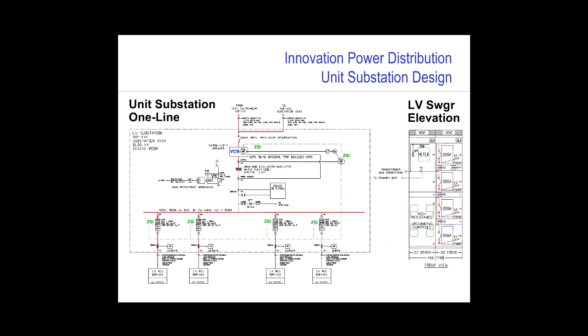So let's summarize what we've discussed today. Let's take a look at, if we had a blank piece of paper, what would today's perfect unit substation look like? Well, I've included here at least my idea of a perfect unit substation. As you can see in the one line, it's fed from a 15 kV source into a load break switch and a primary vacuum circuit breaker with an integral 50/51 tripping device. Followed by that is the transformer, and then feeds the low voltage section, which includes no main breaker but secondary current transformers, and in this case 4 feeder breakers, each with LSI trip units.